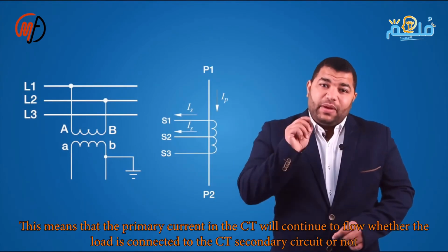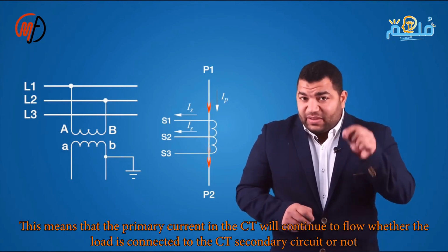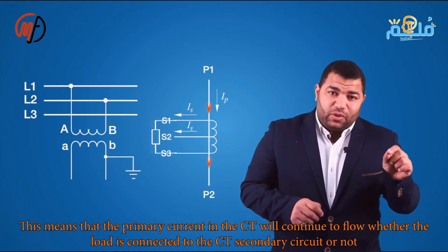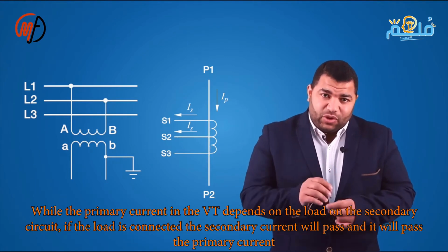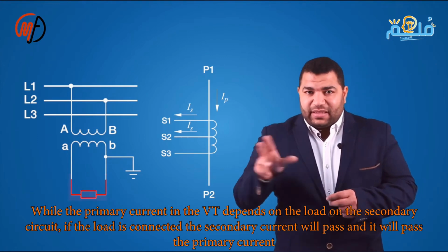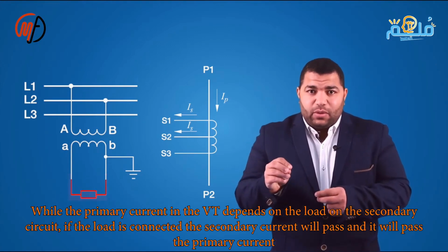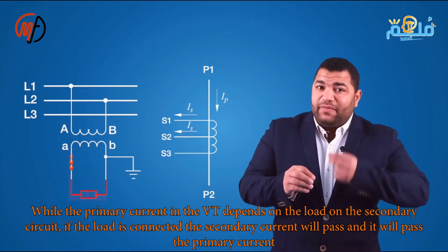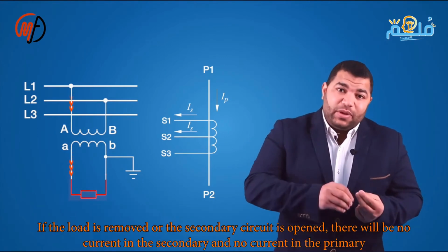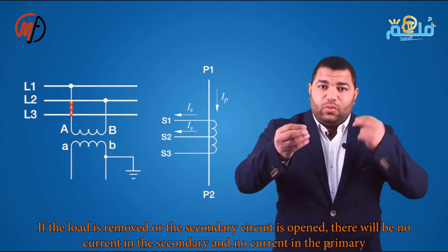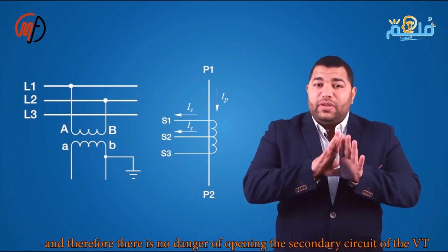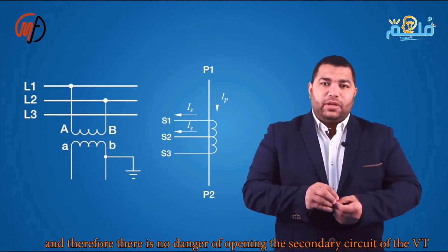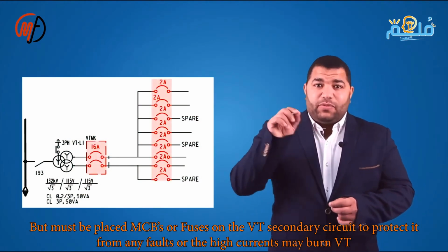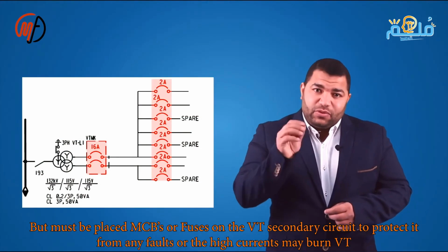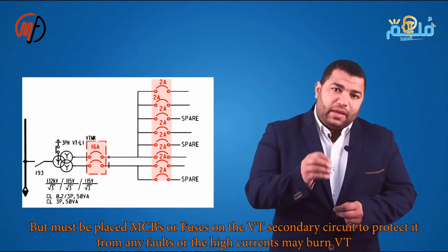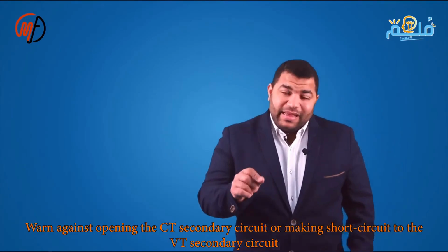This indicates that the current in the primary CT will be present whether the load is connected to the secondary or not, while the current in the primary VT depends on the presence of a load in the secondary. If there is a load in the secondary, a secondary current will be generated, which in turn will create a primary current. If the load is removed, the secondary current will disappear, and consequently the primary current will also go away. Therefore, there is no danger in opening the VT secondary circuit. It is essential to place MCBs or fuses on the VT secondary circuit to protect it from short circuits or damaging high currents. Avoid opening the CT secondary circuit or shorting the VT circuit.